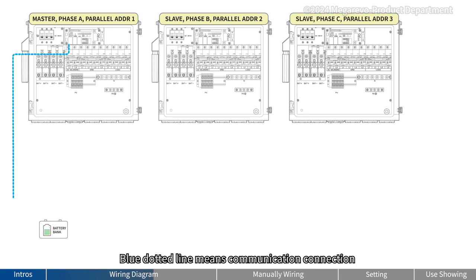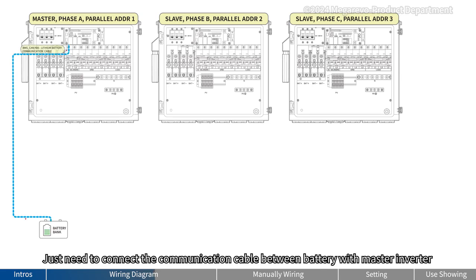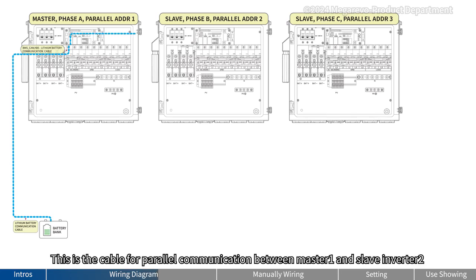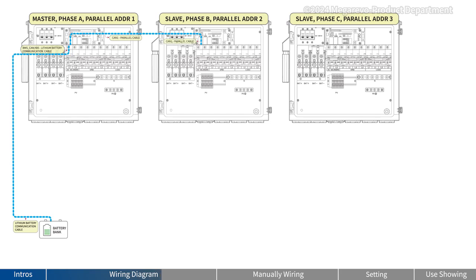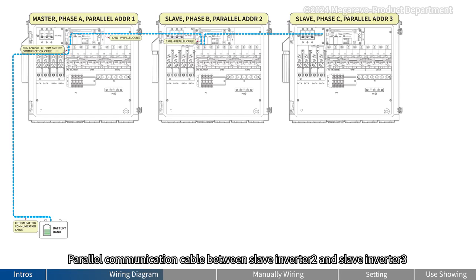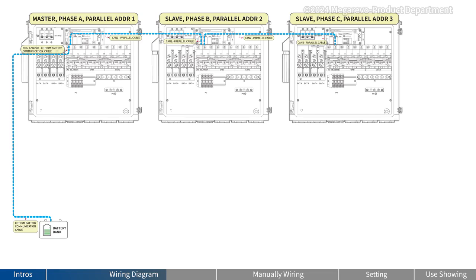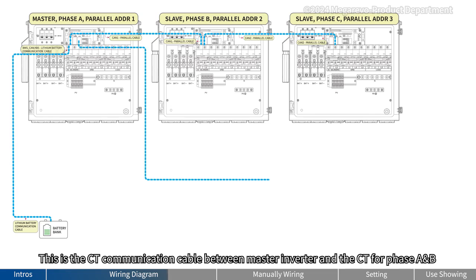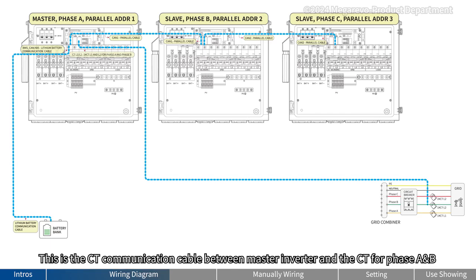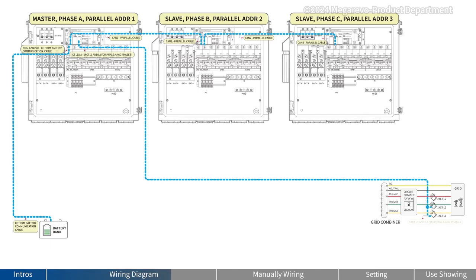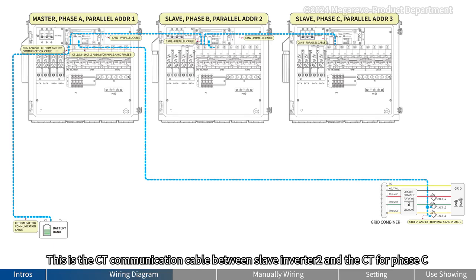Blue dotted line means communication connection. You need to connect the communication cable between the battery and the Master inverter. This is the cable for parallel communication between Master 1 and Slave inverter 2, and the parallel communication cable between Slave inverter 2 and Slave inverter 3. This is the CT communication cable between the Master inverter and the CT for phase A and B. This is the CT communication cable between Slave inverter 2 and the CT for phase C.